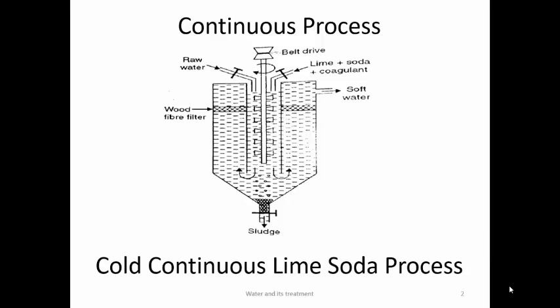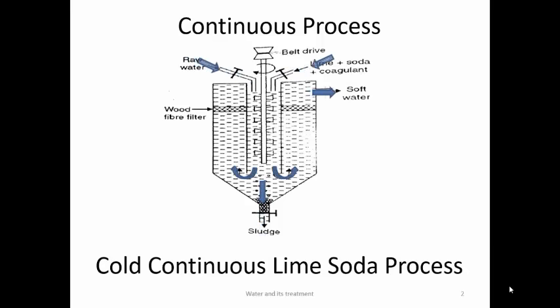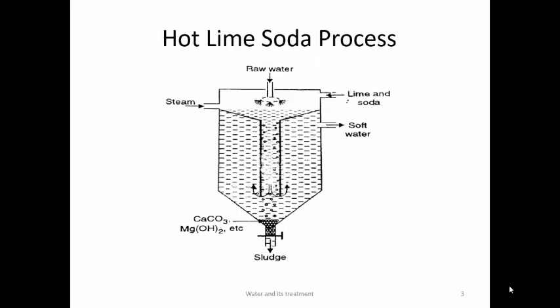Hence, the next process is the continuous process. In the continuous process, raw water and lime-soda plus coagulant are added continuously from separate inlets. These are mixed using a belt drive, and the sludge settles quickly to the bottom. Soft water rises up and is collected into a coaxial chamber. A wood fiber filter placed at one-third height removes suspended particles. Residual hardness is again 30–50 ppm. Shortcomings of cold lime-soda: it is time consuming, gives low residual hardness reduction, and has slow reaction.